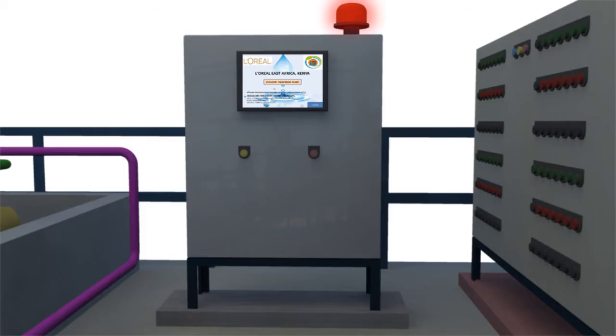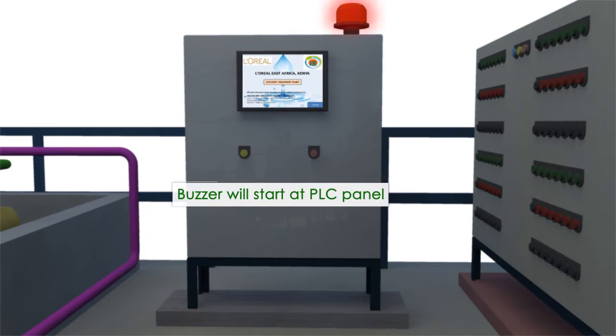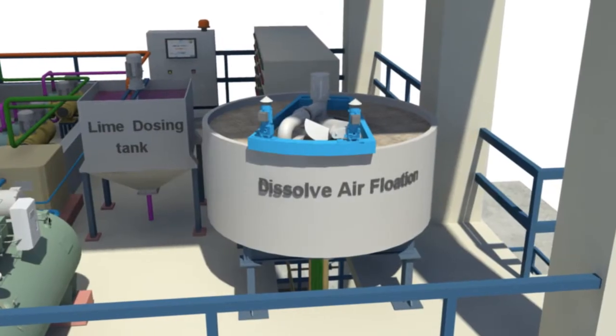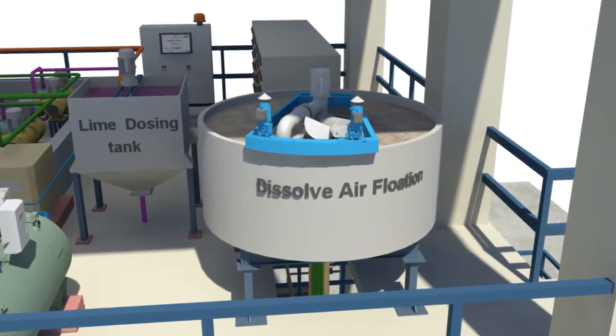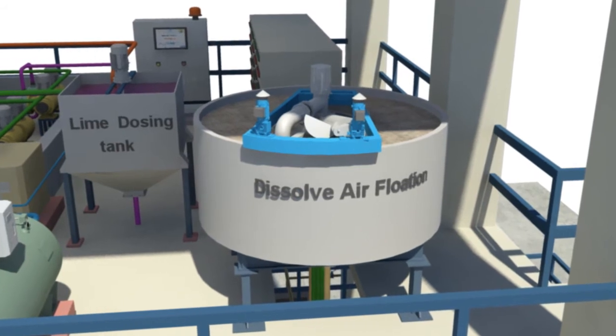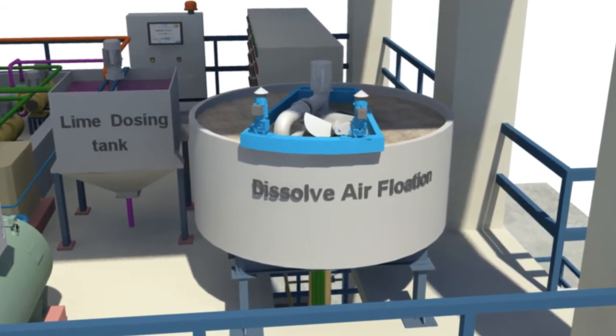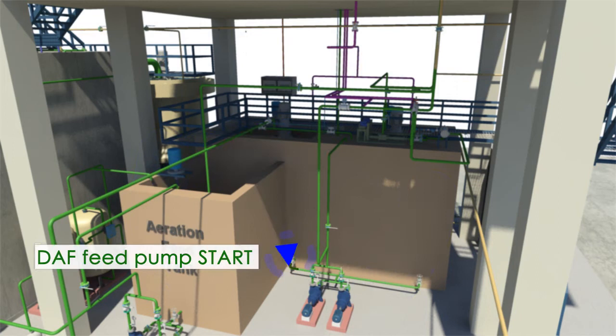After reaching the desired pH level, an indication is given via buzzer on the PLC panel. Once the system reaches this desired level, further action needs to be taken manually. The DAF central drive unit will first need to be started, followed by startup of the air compressor, and then the DAF pump.